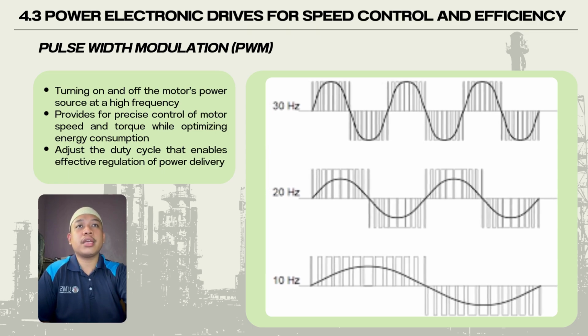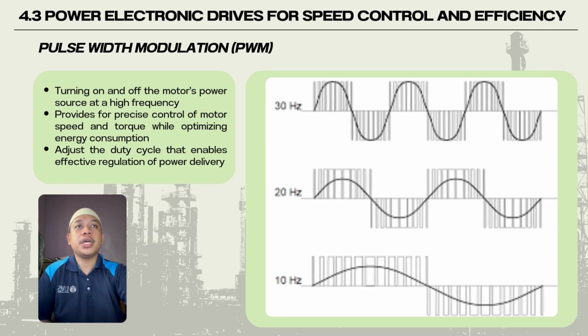We choose one of the techniques of variable frequency drive, VFD, which is pulse width modulation, PWM. It includes turning on and off the motor's power source at high frequency, resulting in pulses. PWM provides for precise control of motor speed and torque while optimizing energy consumption. By controlling the pulse width, a VFD may offer exact power output, ensuring that the motor runs smoothly under varying loads and conditions. This method greatly minimizes power losses when compared to standard control systems, making it an effective alternative for industrial and commercial applications.